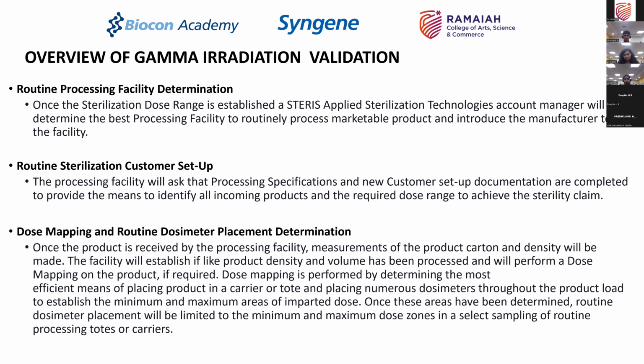if they do not have that kind of data, and while your tote size or whatever you use is fitting within their carrier, but your carton size and volume and density are different from what they have processed in the past, they will perform what is called a dose mapping. Now, this is very similar to our biological indicator placement on a full load at different places to determine whether you have achieved the right doses and what is the maximum dose that you have achieved in that load area, what is the minimum dose which you have achieved.